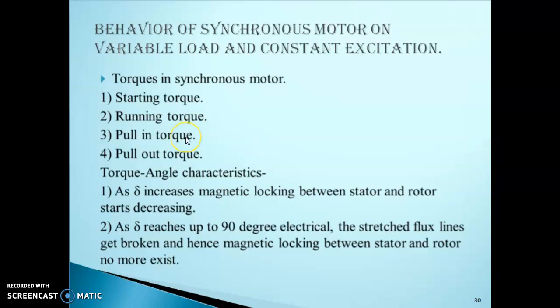Then pull-in torque. Now we know that initially the synchronous motor is rotated at a speed slightly less than the synchronous speed. When the speed is near synchronous, excitation is switched on and the motor pulls into synchronism and starts rotating at synchronous speed. The amount of torque developed by the motor at that time is called the pull-in torque. Means when our synchronous motor gets pulled into synchronism, that instant's torque is called the pull-in torque.